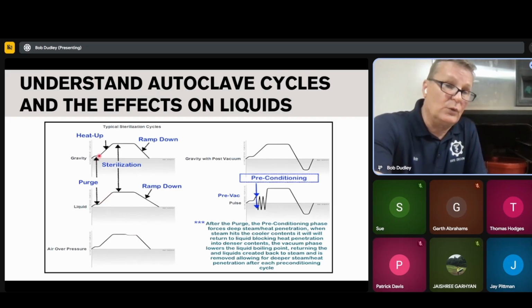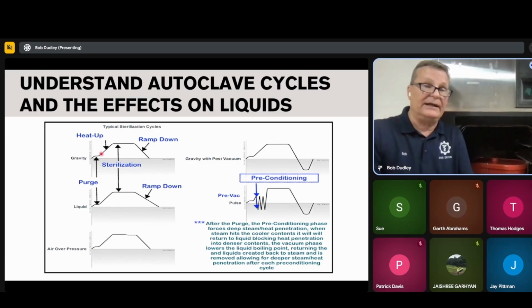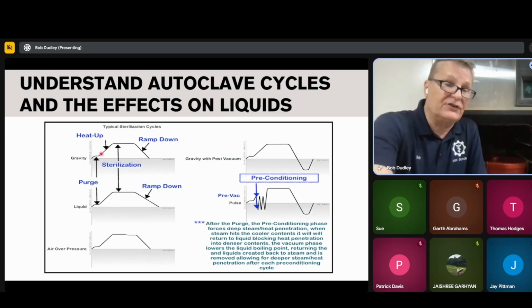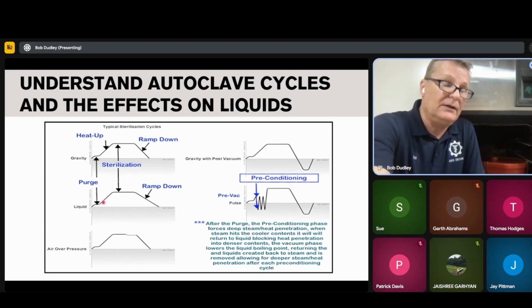So with the gravity and the liquid, what happens is it's going to pump in 2 or 3 psi right here, and then it's going to start heating up, and then it stops for a second. And if you ever listen to the autoclave, you'll hear the steam go in, and then you'll hear it click stop. And what's happening, especially with the newer autoclaves, is it's going through a little check here. It's going to come up and pump a little bit in, and the autoclave should check to see whether or not we're maintaining this heat. It's going to measure the amount of drop.